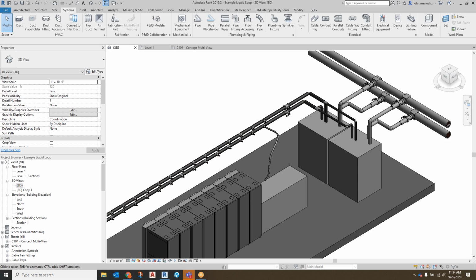For a given heat load, you'll need a larger size pipe. In the original design, to future-proof the space, you'll have fittings or nipples on your piping in different sizes to accommodate branch lines running to heat exchangers, rear door heat exchangers, or whatever is in the middle of the floor. So it'll come down to a pipe size per kW.